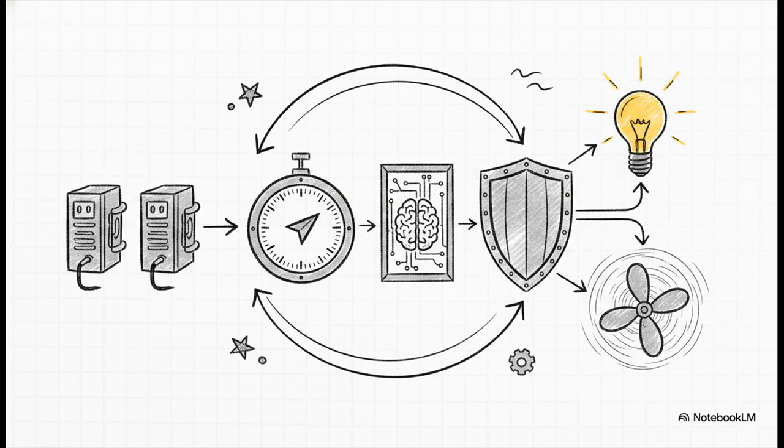When you step back and look at it, every single system we've talked about today exists just to solve a problem created by the system before it. Redundancy demands parallel running. Parallel running demands synchronized governors and AVRs. That synchronization requires Droop to share the load. Droop needs the PMS to fix the frequency drift. And that whole web requires surgical protection. It is just a massive, cascading loop, all designed to do one thing: keep those propellers turning.